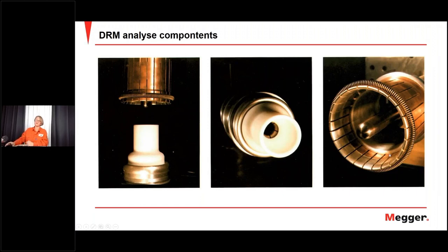And this you can also evaluate a little bit on the graph you get from the DRM measurement. The white here is the nozzle, and that is used for controlling the gas, but also for protecting the main contact from the arcing. So the separation, the arcing, is done inside here. If you open up an old breaker, this nozzle will not look like this. It will be much more worn out. This is like a really new condition. You can also see on the contacts that it's really nice and clean and no worn contacts.